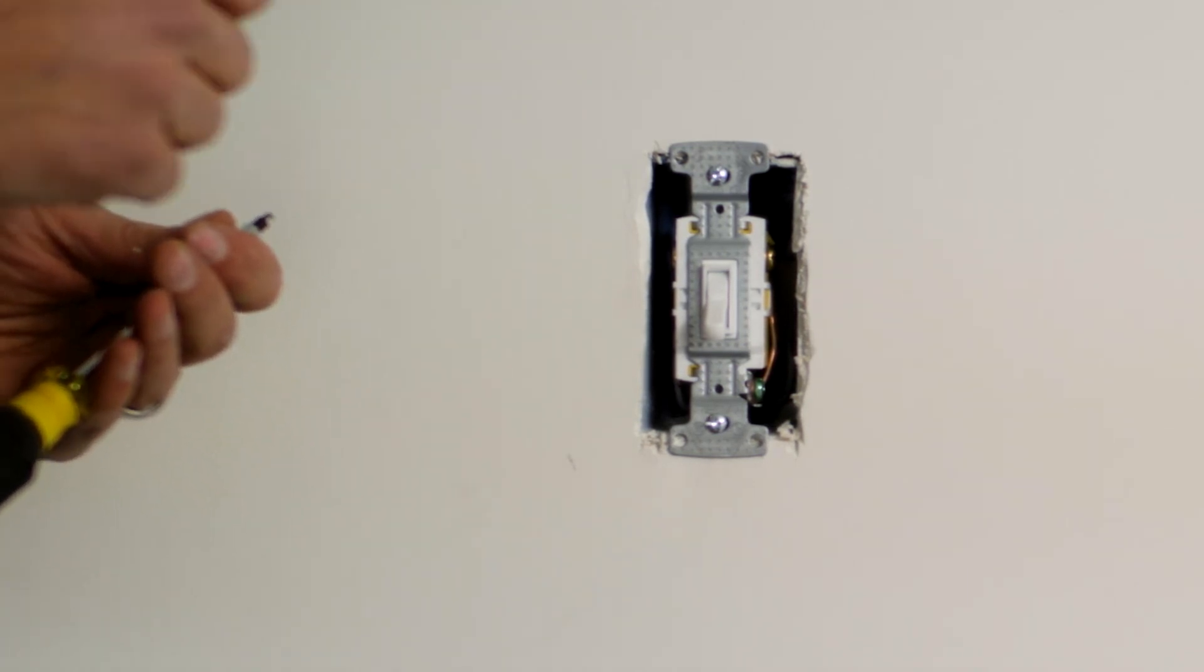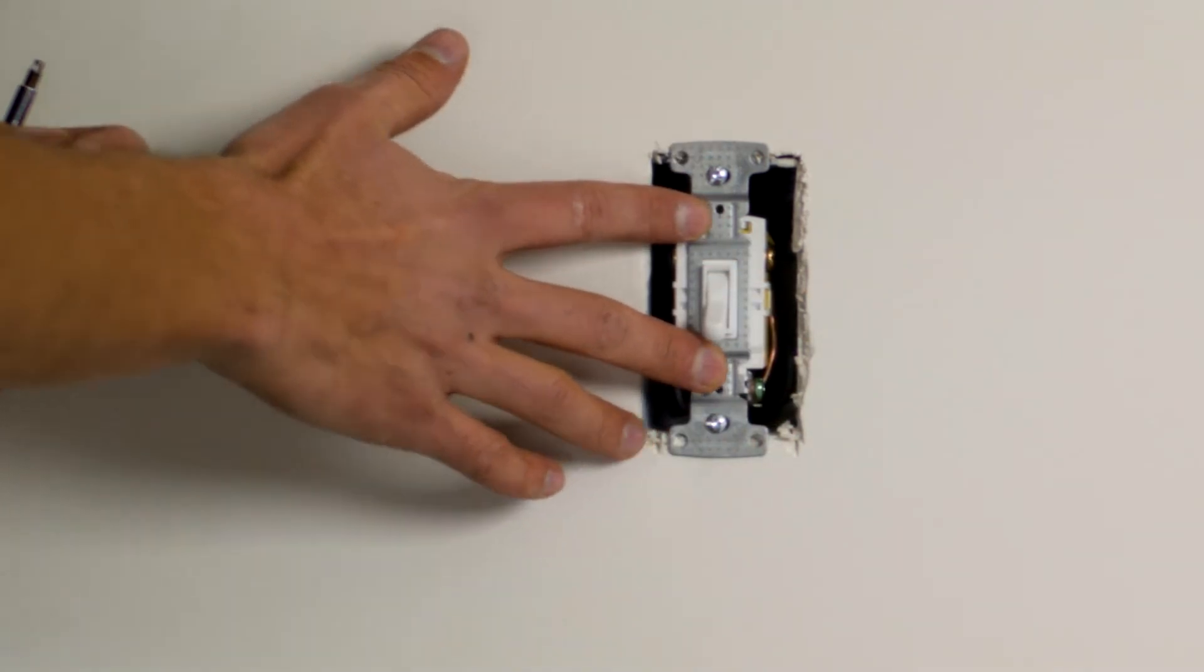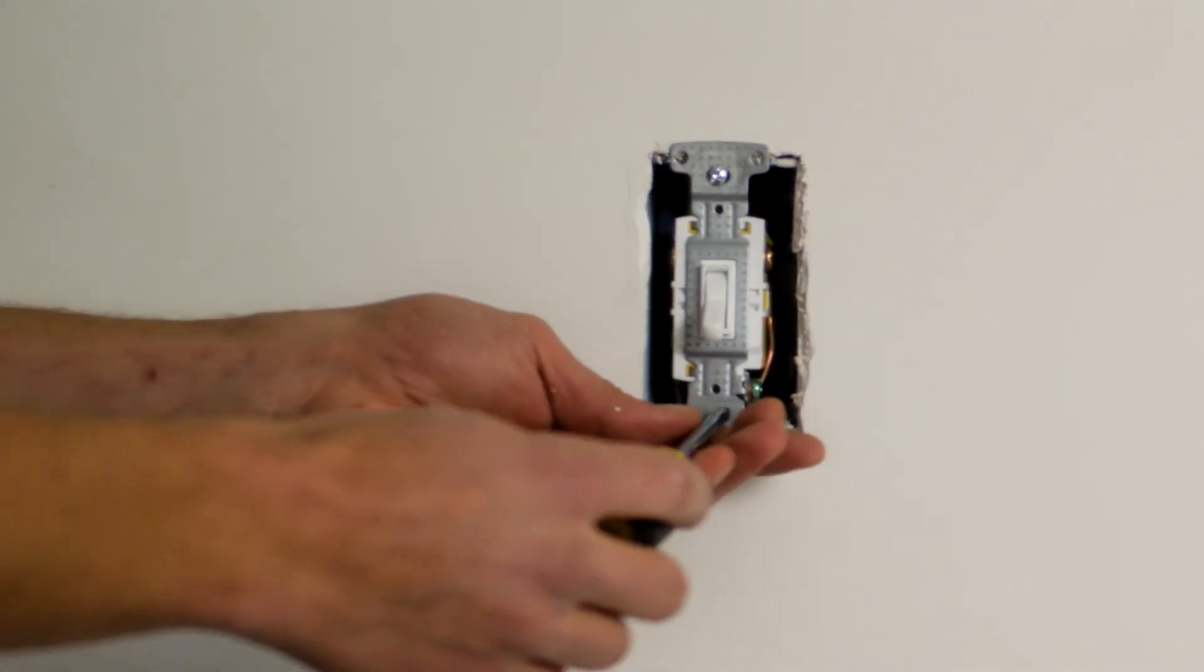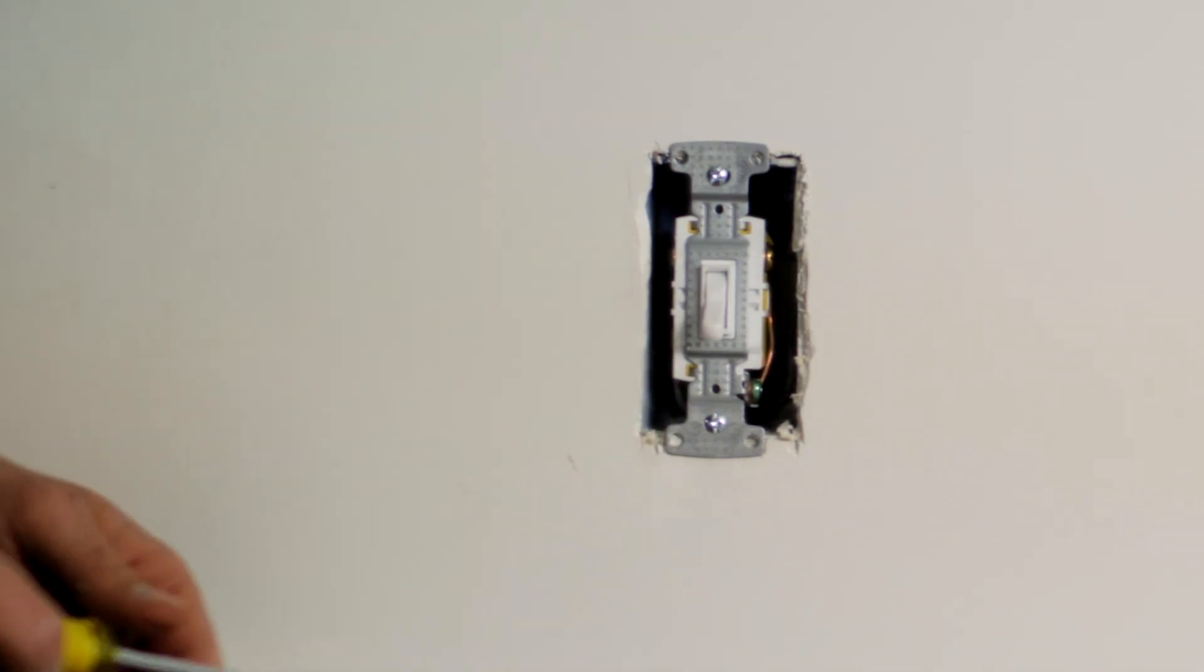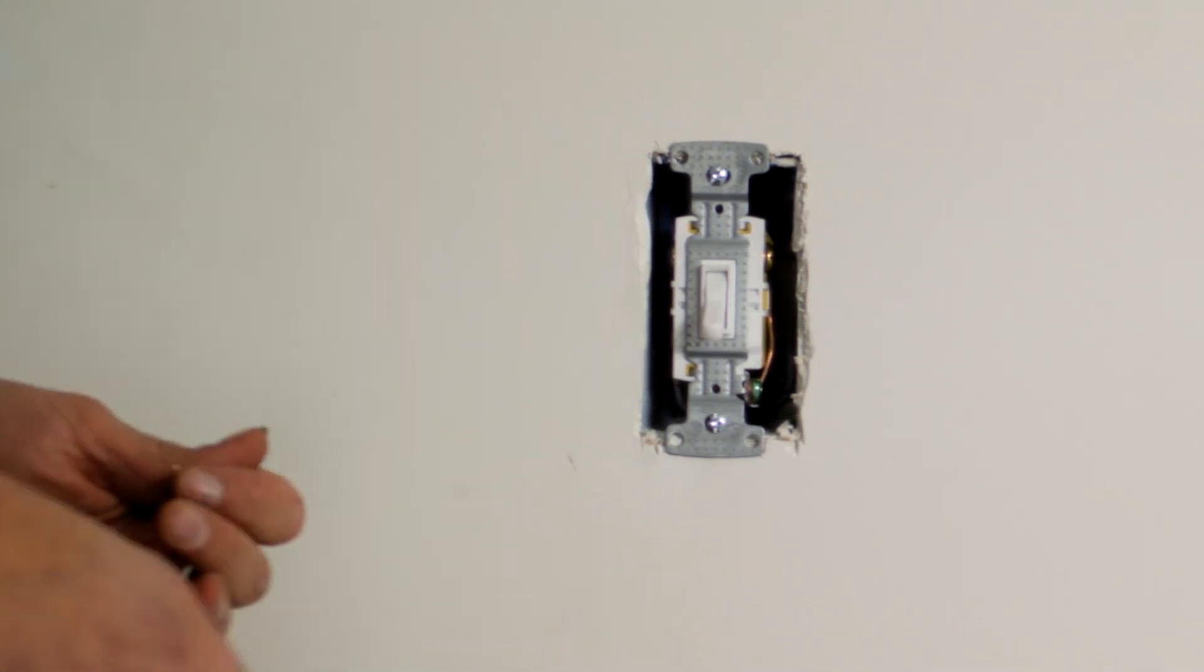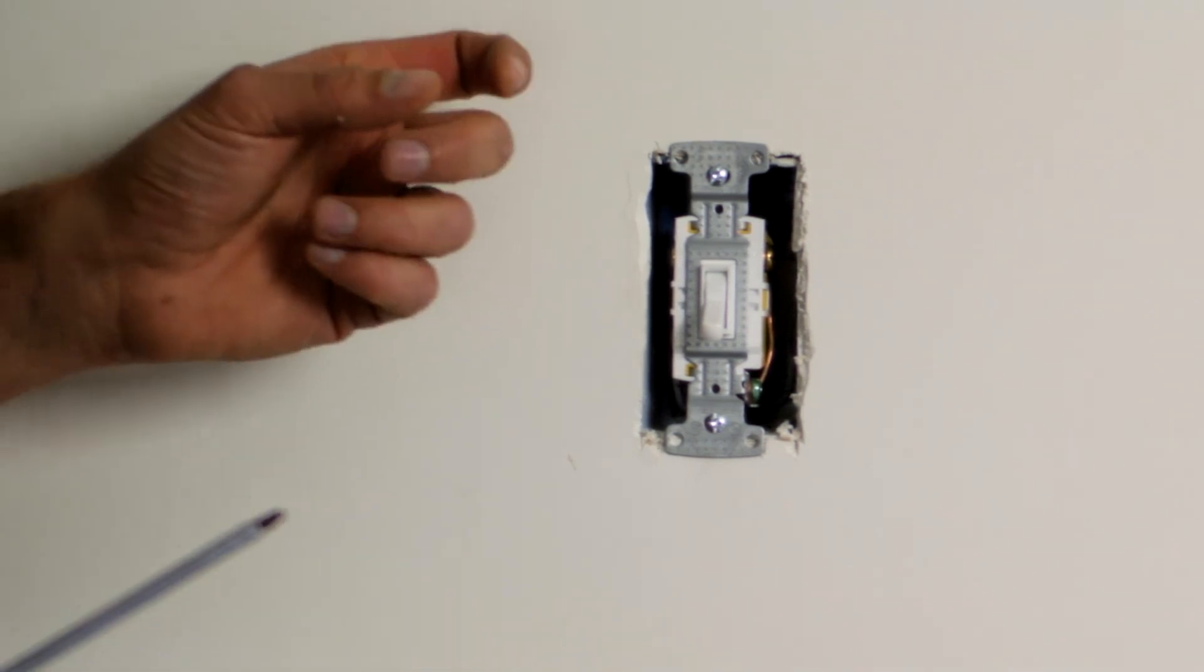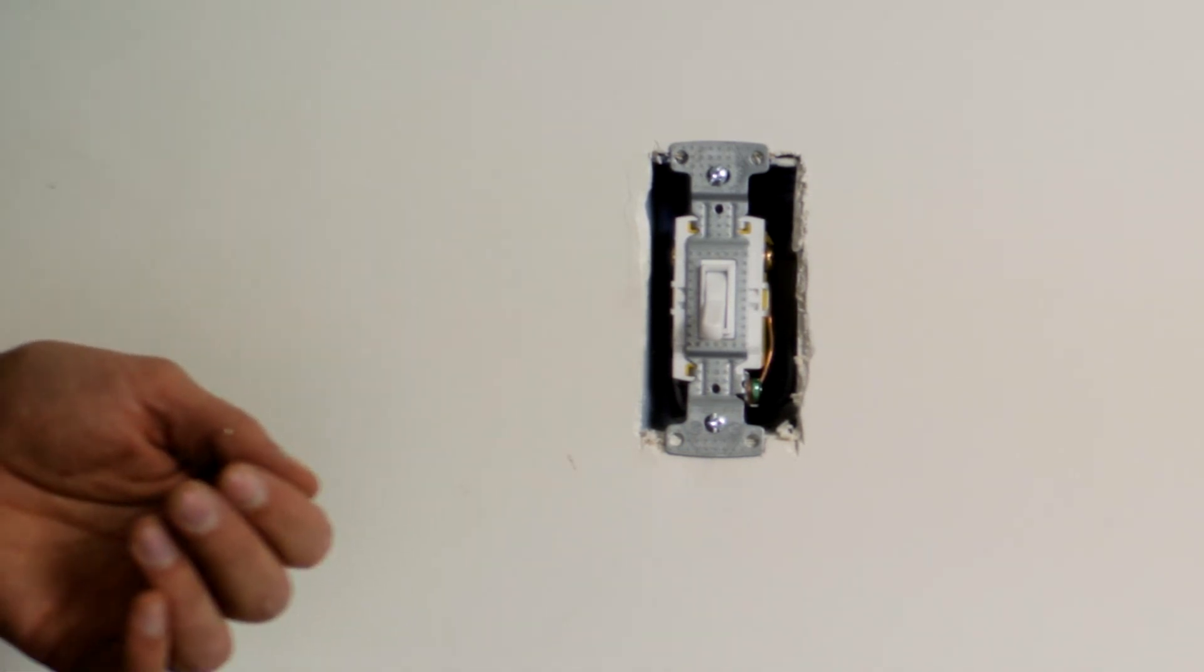In this case, it's secure. I've not deformed the switch at all by over-securing it. There's no play left in the switch, and I've got a good, clean finish. Something we mentioned on the rough-in is boxes spaced properly such that the yoke of the device secures to the box in a secure and tight manner. This being a non-combustible material, we've got a maximum of quarter inch that the box can be recessed behind the finished surface of the drywall.